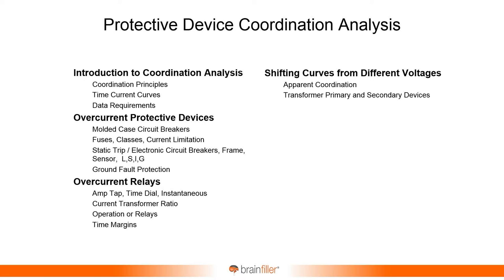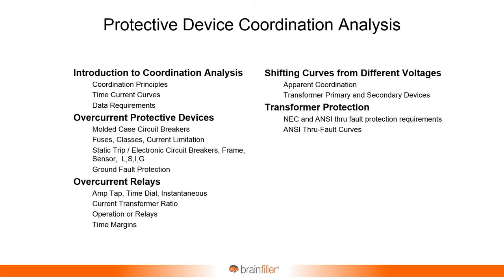This happens regularly when comparing a transformer's primary and secondary devices. We're also going to look at protecting transformers with overcurrent devices. The National Electrical Code has criteria in table 450.3(a) and (b), which really just gives what I refer to as a backstop for protection. In my opinion, the NEC doesn't give good guidance for protecting transformers. The preferred, better method is to use what's known as an ANSI through-fault curve, and I'll show you how to use this with examples throughout the course.